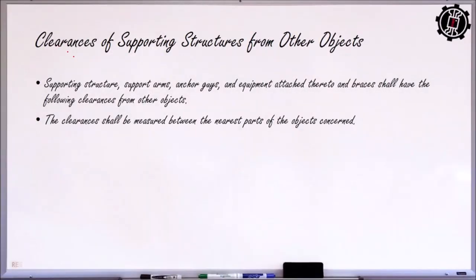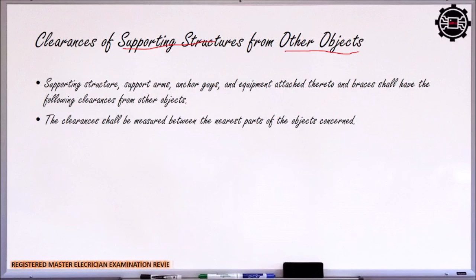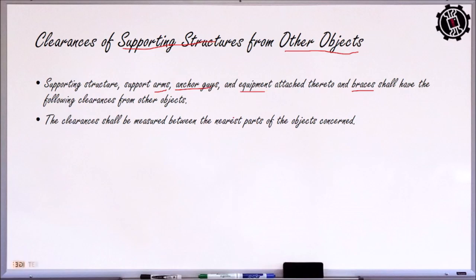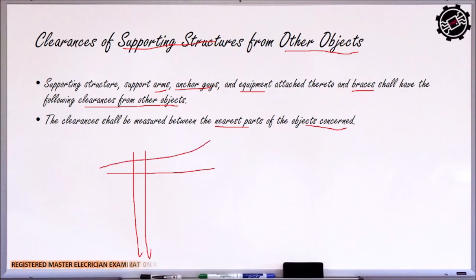Okay. So, clearances of supporting structures from other objects. So, when we say supporting structures, the cross arm, yung mga nakakabit sa cross arm, yung mga bolts, yung mismong poste. So, those are the supporting structure. Ito include arms, anchor guys, and the equipment itself. So, kasama yung mga braces, and they must follow the clearances from other objects. So, the clearances shall be measured between the nearest part of the objects concerned. No? So, kunyari, kanina yung example ko kanina, sabihin na nating cross arm dito, tapos may nakalawit dito na insulator. So, yung clearance na sinasabi is hindi itong cross arm, yung pinakamababa na object or the supporting structure, which is the insulator, full insulator. So, yan yung consider natin as the clearance.